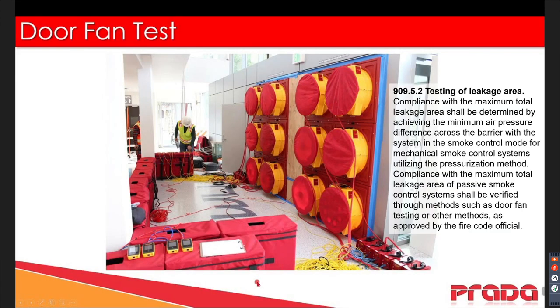But if it's questionable, the code does allow the jurisdiction to require leakage testing, and this is kind of a big deal. You know, these door fan tests are pretty significant. They use a pressurization method where they measure leakage, and then a whole calculation is required to show the size of the smoke barrier, the amount of leakage, and determine based on a calculation whether that's sufficient or too much. And we did do that in a facility up north.